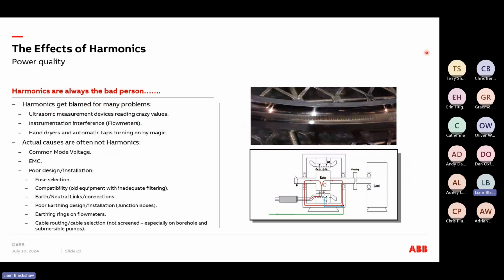But when we look at power quality as well, harmonics always seems to be the bad person, and it does get blamed for many problems, where you might have things reading crazy values, and this all comes back to: is it EMC or is it harmonics? So it's always worth remembering that things like this may not necessarily be harmonics, and are often not harmonics. It could be things like common mode voltage, again EMC, but it also could come down to the design or installation of the system. It might be poor, where things like fuse selection have not been done correctly in terms of compatibility. You've got some old equipment on there that's not been adequately filtered.